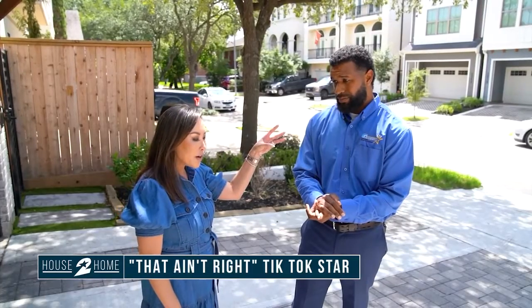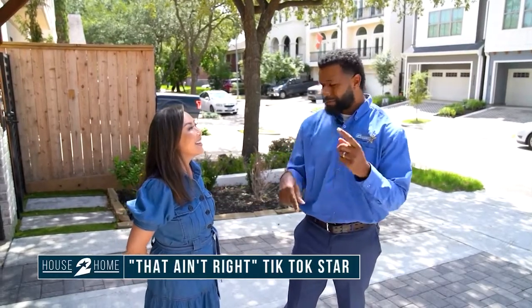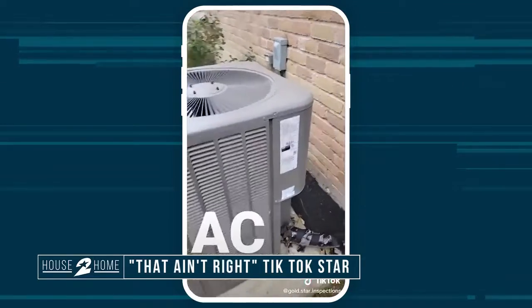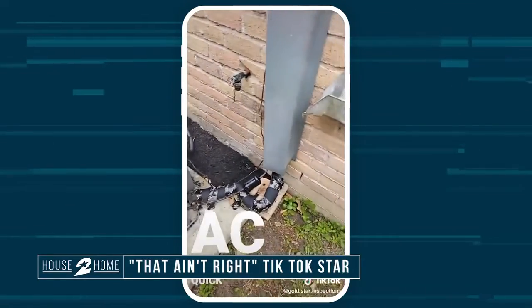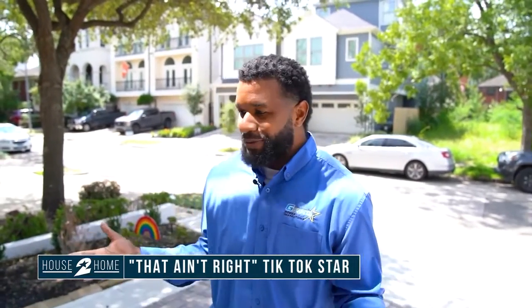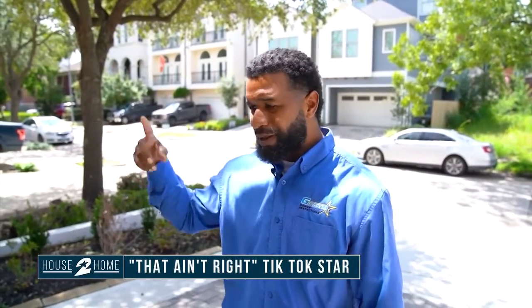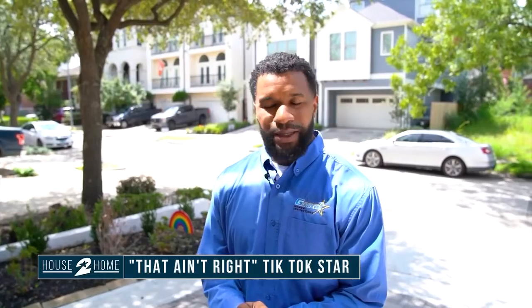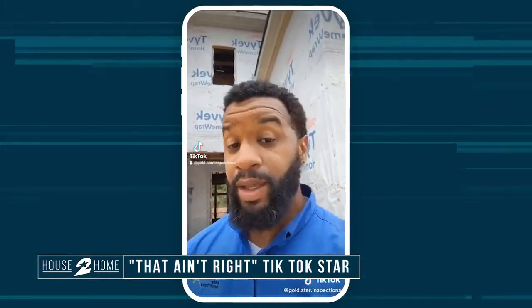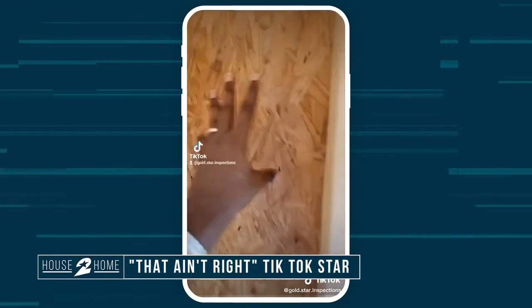Tell me the top 3 things you find in new construction that you put on TikTok and Instagram. Let me tell you one thing, a lot of people don't realize, AC. Almost every report, the AC is not cooling the way it's supposed to be. Even brand new AC? Brand new. If they don't put enough refrigerant in it, it ain't cooling. So you're in a new home, it's new, and your electrical bill running up. So it's a bunch of AC, infrared camera, insulation. Missing insulation. That ain't right, y'all. That ain't right. In walls, ceilings, missing insulation.